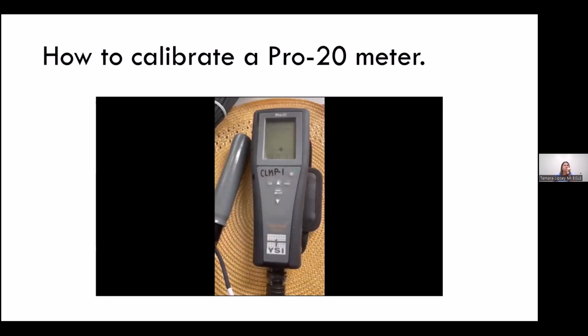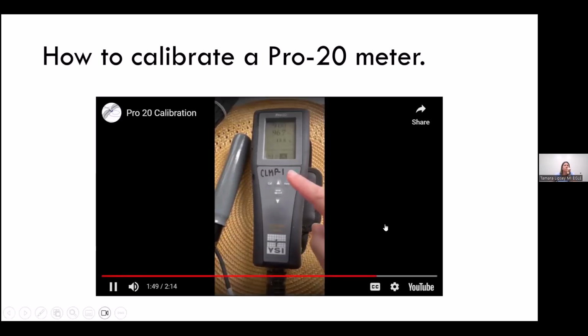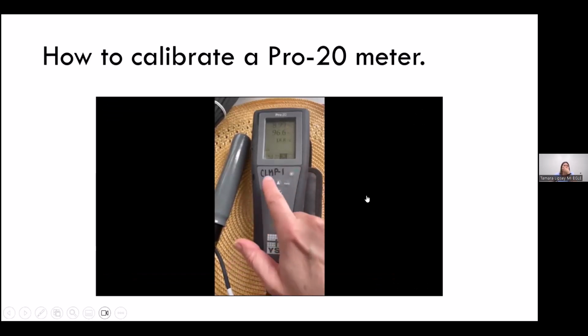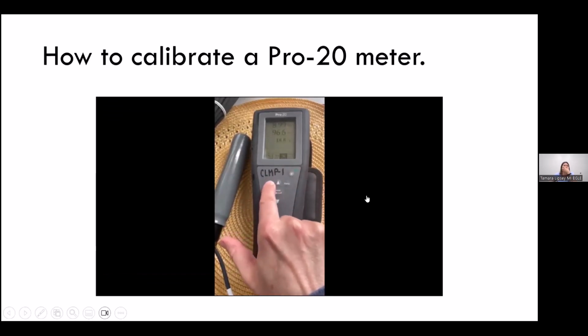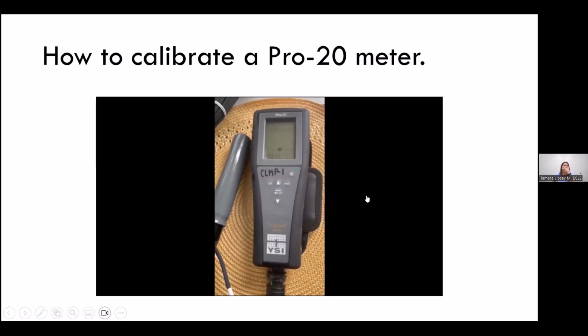And then it will say calibrating percent dissolved oxygen until it says calibration successful. And then you're all set. Notice it did go away, the calibration successful. So if it's taking some time and you look away, you might miss that. But if you wanted to double check, all you do is hit calibration again, hold it, calibration successful, and you're ready to go. Have fun.